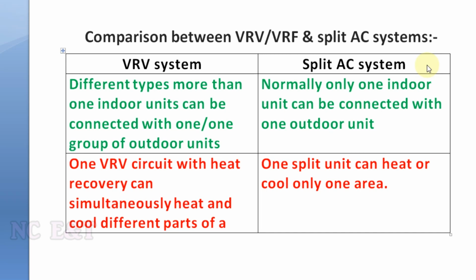Also, we can see some comparison between the VRV and VRF system and the split AC system. Point number 1, in VRV and VRF system, as we discussed before, different types and different numbers of indoor units can be connected to a single outdoor unit or a group of outdoor units through a single network of piping. Number 2, one VRV circuit with heat recovery can simultaneously heat and cool different parts of a circuit, but in a split system it is not possible.